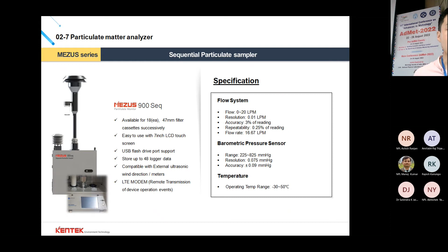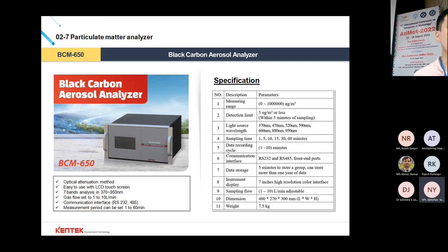And this is the black carbon aerosol analyzer. This analyzer uses the optical attenuation method, and the black carbon is analyzed at 7 wavelength bands from 370 to 950 nanometers.